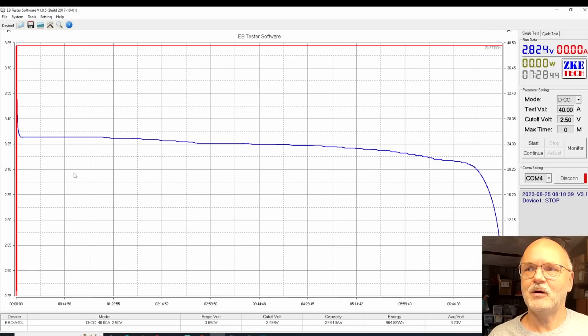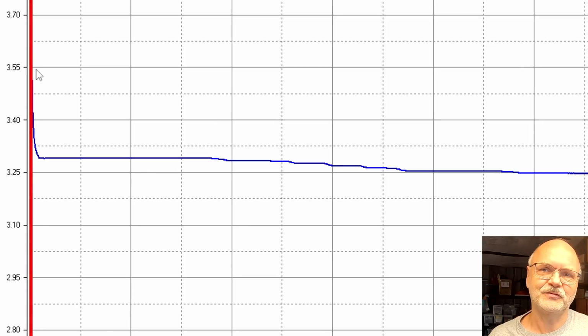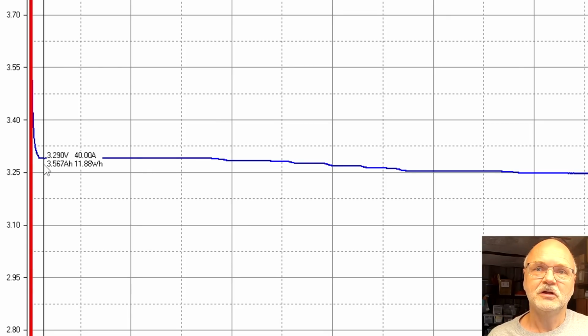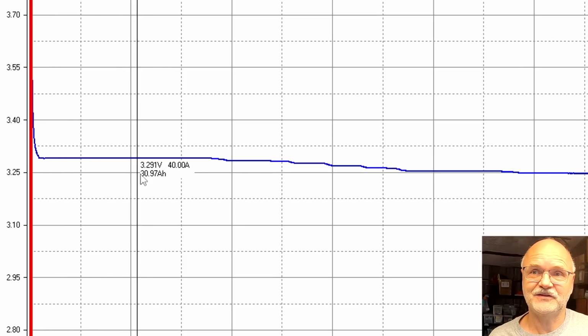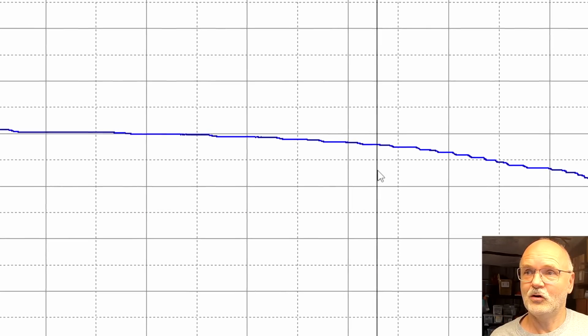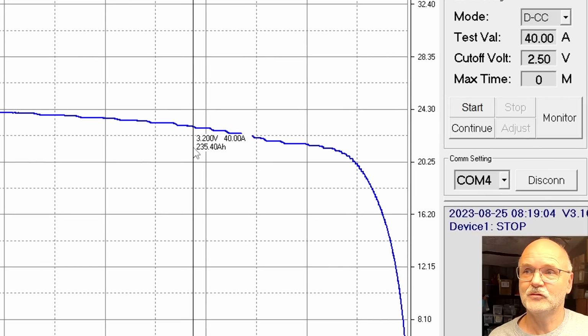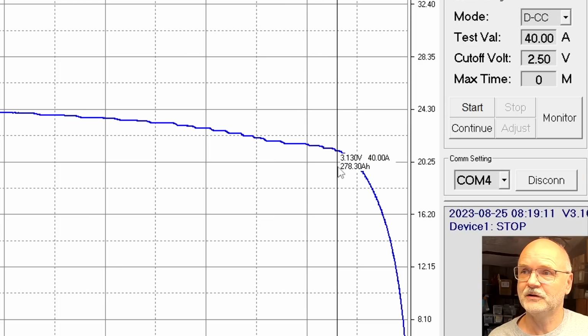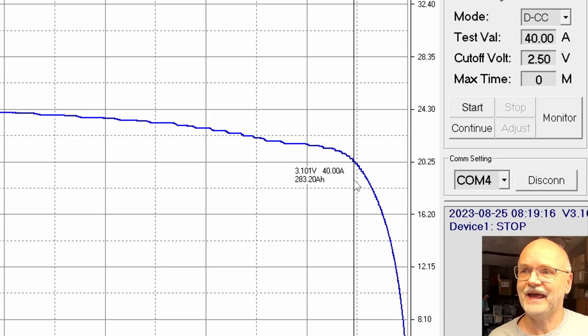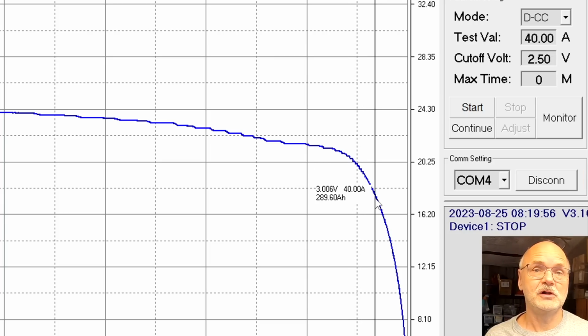Duh, oh well, we can see our beautiful discharge curve of the lithium iron phosphate battery number 142 in my pack. Here at the beginning we've got this steep drop of voltage down to 3.29 volts and then it stays flat all the way, and we are here at 3.2 volts still at 235 ampere hours. Then further down to 3.1 volts, we are at 278 ampere hours. And 3 volts is usually where I stop discharging my batteries here in my production system, in the battery shelf and the power wall. It still gives you a tiny amount of capacity left in case you need it, but usually 3 volts is a very defined spot on the steep area of the curve already.